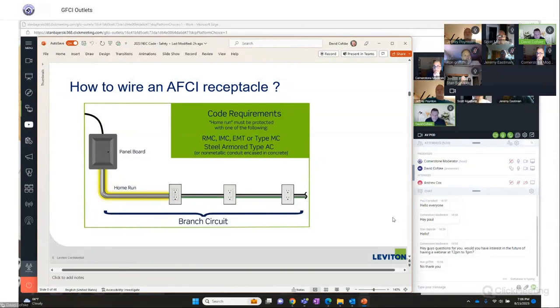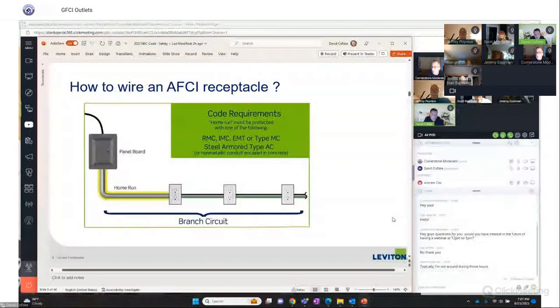When you're talking about AFCIs in device form, like a receptacle, I included this list of how you have to run an AFCI device in a home. You come out of your panel and you need to leave that metal enclosure with either rigid metal conduit (RMC), intermediate metal conduit, EMT (electrical metallic tubing), or a cable like metal-clad steel armored cable, from that panel to the AFCI device. That needs to be bonded. After that, you can run Romex, which is a non-metallic conductor. It's really the only way for that AFCI device to effectively work.